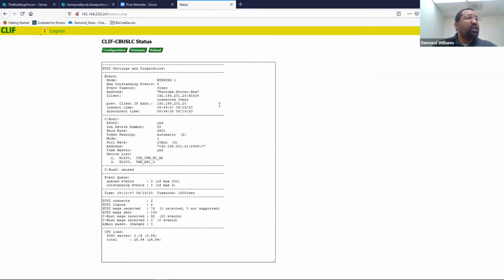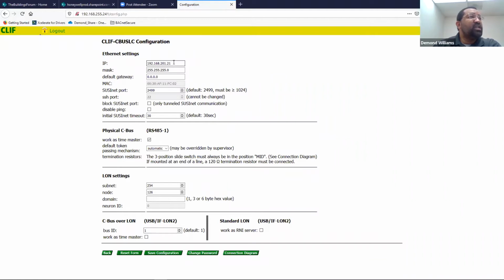When you first log in, it kind of gives you a quick overview of how the system is set up. The only part of the configuration that you will pretty much be touching once you go into configuration is basically setting what the IP address is for the physical Ethernet port that is on the controller itself. Once you give it that IP address, you're good to connect it to a CIPer 50, a Jace 8000, or directly to the supervisor. Your CIPer 50 actually comes pre-licensed with the Centraline Honeywell C-Bus driver.